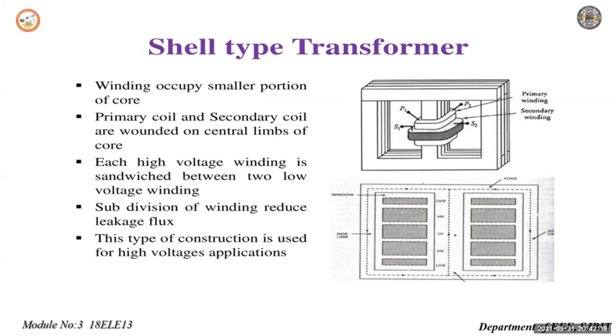How do you compare the core type with the shell type? In the core type, the winding encircles the core, whereas in the shell type, the core encircles most part of the windings. The second point: cylindrical type coils are used in the core type. In the shell type, generally multi-layer disc type or sandwich coils are used. In the core type, windings are distributed, but here the windings are surrounded by the core. In the core type, the coils can be easily removed from the maintenance point of view.